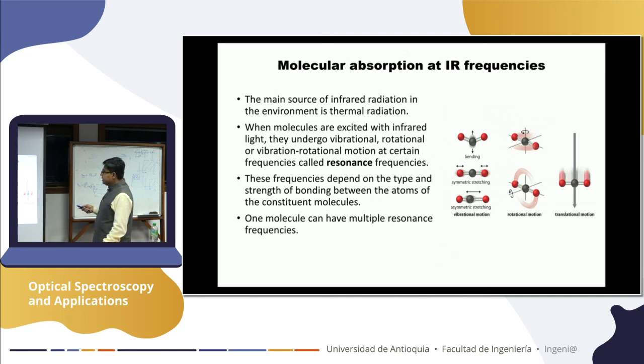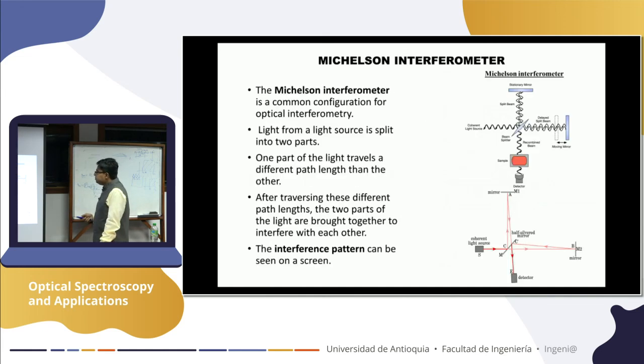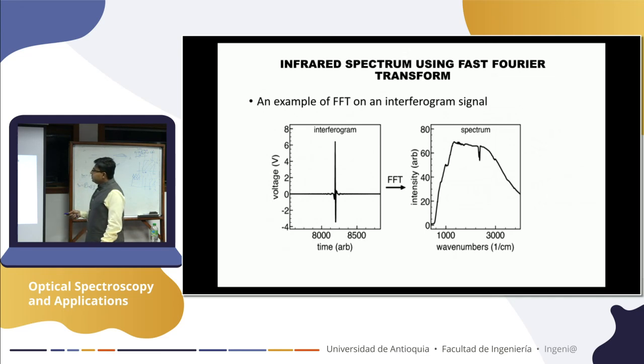So we went back to infrared light and excited various vibrational modes. To overcome the problem of needing many wavelengths, we introduced a Michelson interferometer, where your light comes through two different paths and interferes on the detector, and then you do a Fourier transformation of that, the interferogram.